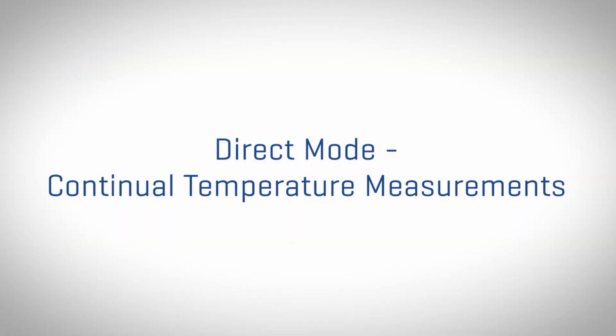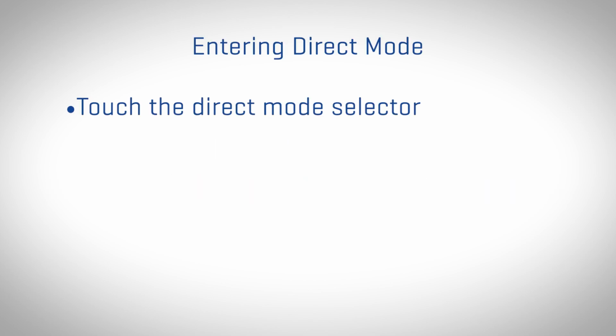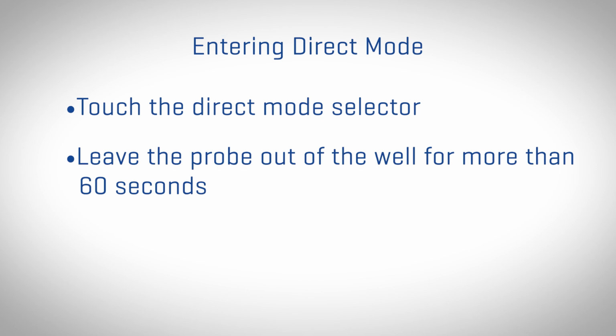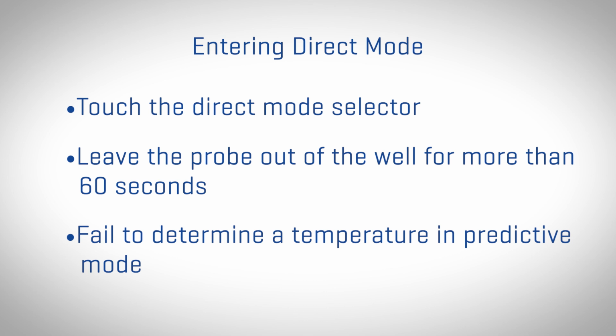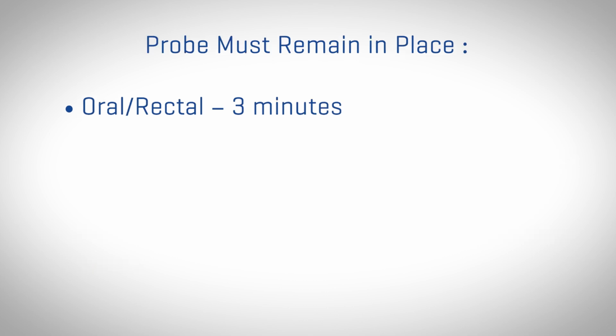Now let's review direct mode, which provides continual temperature measurements. There are 3 ways to enter direct mode: touching the direct mode selector, the snail icon, after you complete a predictive mode measurement; leaving the probe out of the well for more than 60 seconds; or failing to determine a temperature while in predictive mode. To take an oral or rectal temperature in direct mode, the probe must remain in place for 3 minutes, and axillary temperature for 5 minutes.